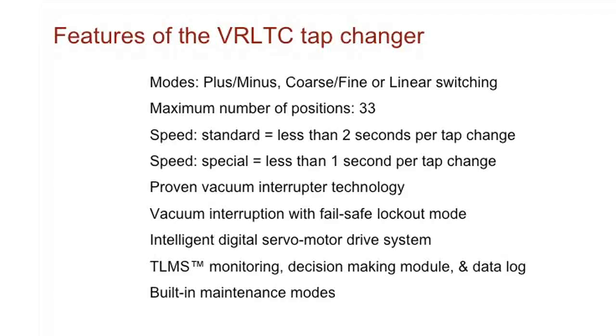Basically, it's a 33 position. We have it where it'll operate in 2 seconds, which is the time it takes to make the tap change, or by special order, we can get it in 1 second, which is a special condition. Proven vacuum interrupter technology, we've had that for years. They've implemented that in the tap changer. Also a fail-safe lockout mode, which is critical as well. Intelligent servo motors, or the drive motors that are operating it. And then we have what we call a TLMS, which is a monitoring and decision-making computer, basically, on board, that you can set up to monitor various different modes of the LTC.